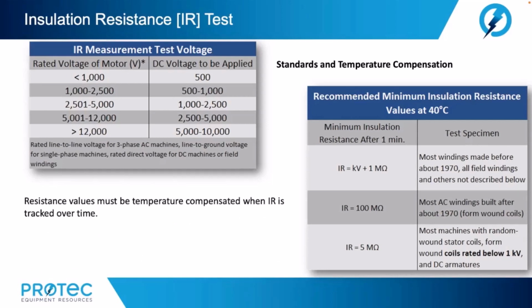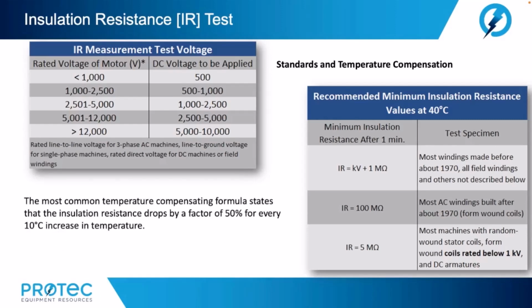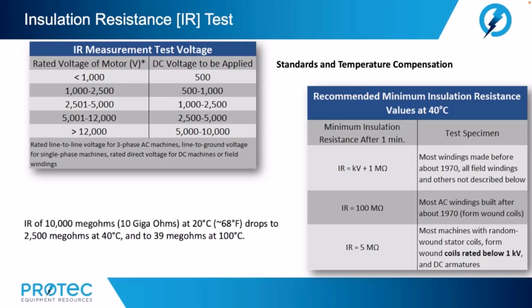Resistance values must be temperature compensated when insulation resistance is tracked over time. The temperature must also be above the dew point for accurate comparisons of results. The most common temperature compensating formula states that the insulation resistance drops by a factor of 50% for every 10 degrees C increase in temperature. Therefore, the insulation properties drop precipitously as the temperature rises. Insulation resistance of 10,000 megohms, 10 gigohms, at 20 degrees C, which is about 68 degrees Fahrenheit, drops to 2,500 megohms at 40 degrees C and to 39 megohms at 100 degrees C.